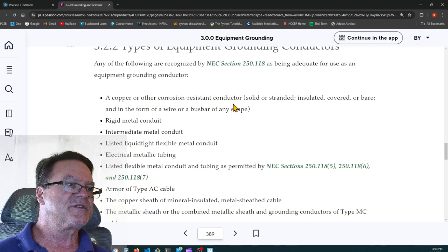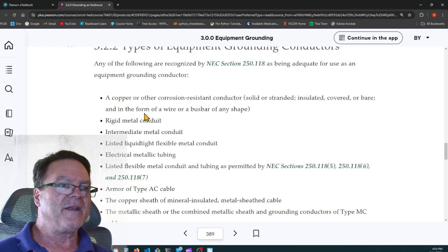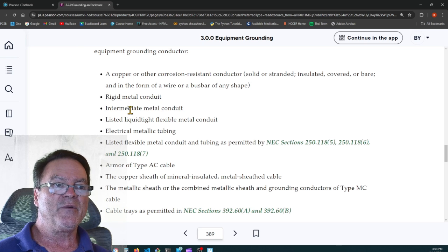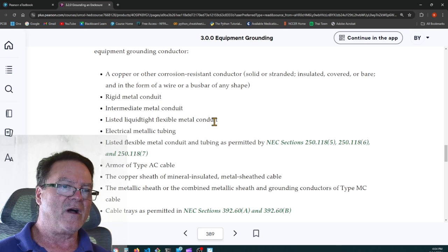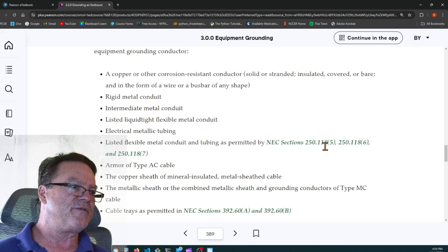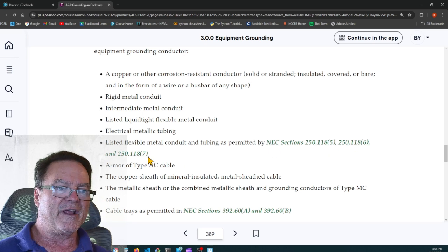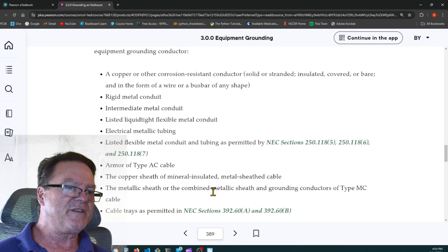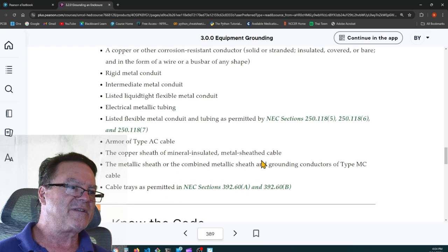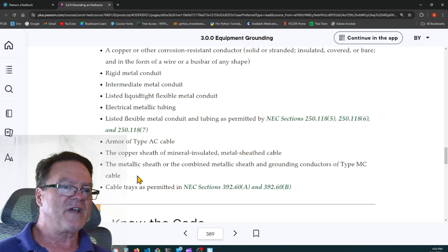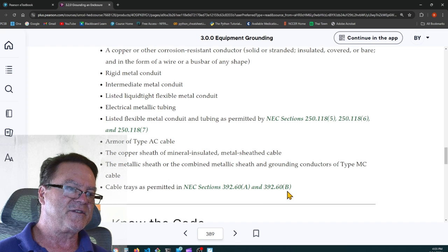Use a copper or other corrosion resistant conductor, solid or stranded, insulated, covered, or bare, and in the form of a wire or a bus bar of any shape. You can use rigid metal conduit, intermediate metal conduit, listed liquid tight flexible metal conduit, electrical metallic tubing, listed flexible metal conduit and tubing as permitted by NEC section 250.118.5, 118.6, 118.7, armored cable, the copper sheath of mineral insulated metal sheath cable, metallic sheath or the combined metallic sheath and grounding conductors of type MC cable or cable tray as permitted in NEC section 392.60A and 60B.